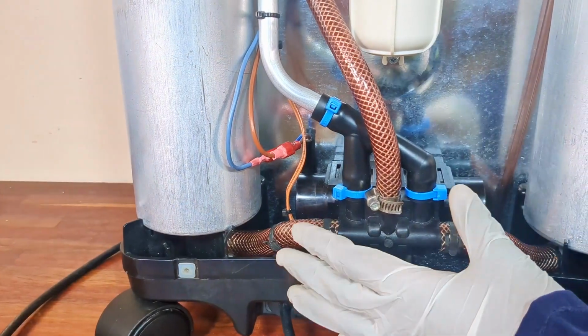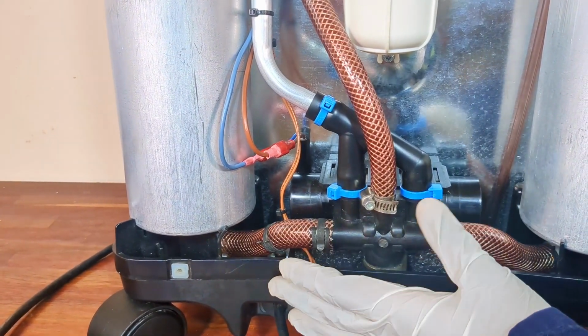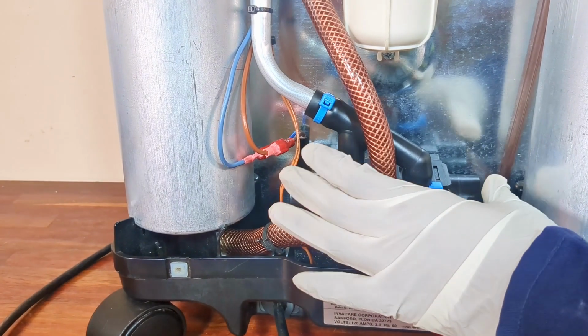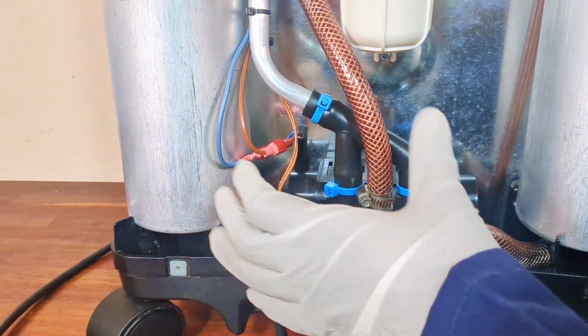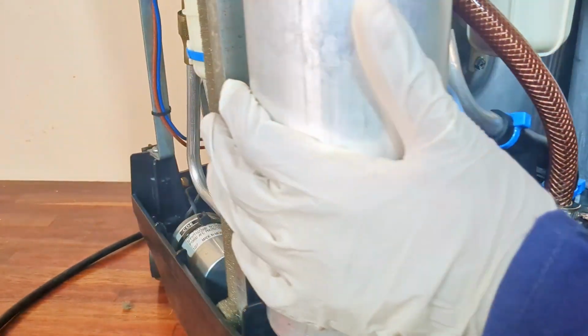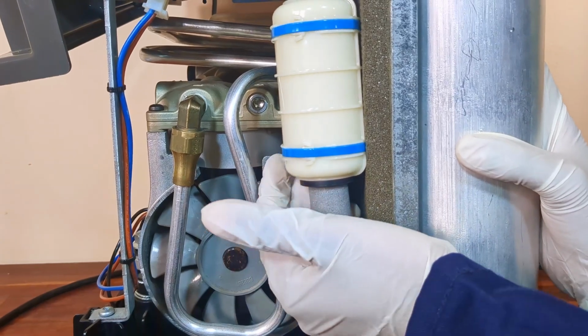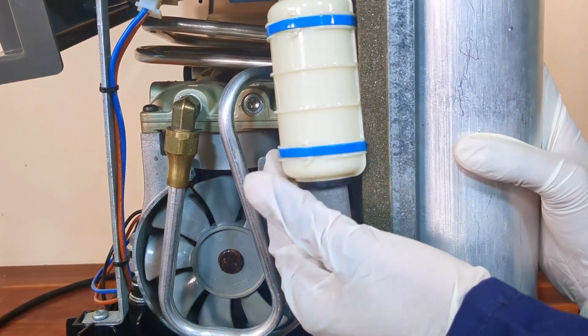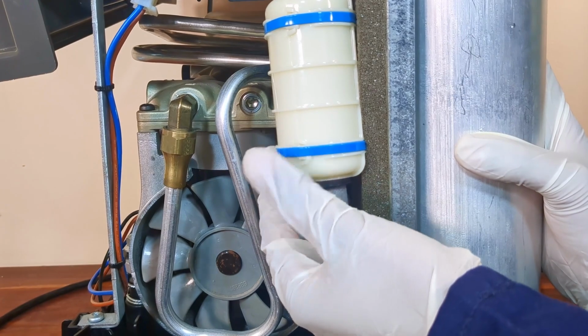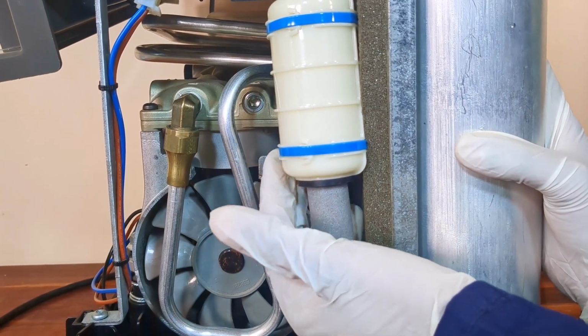The nitrogen that was separated out is released back into the room air through the four-way solenoid valve and the exhaust system. A muffler is located at the exhaust end of the valve to reduce the sound of the exhaust as it exits the concentrator. And that concludes the pneumatic system of this oxygen concentrator.